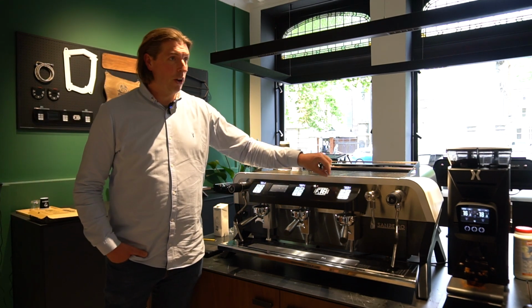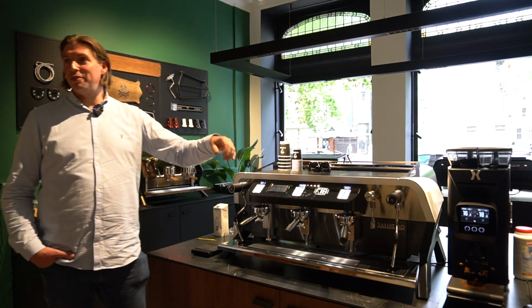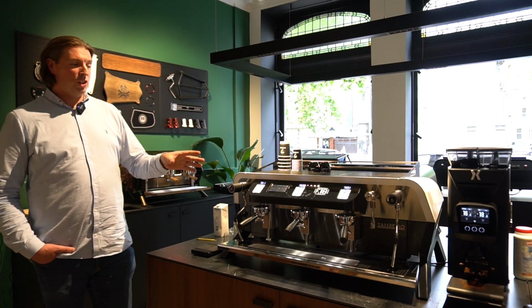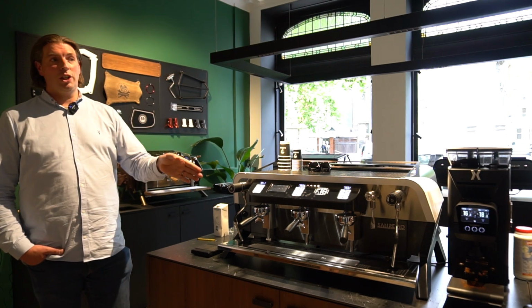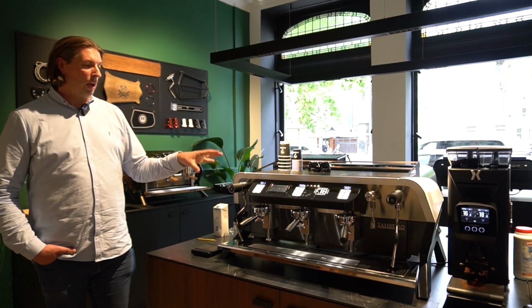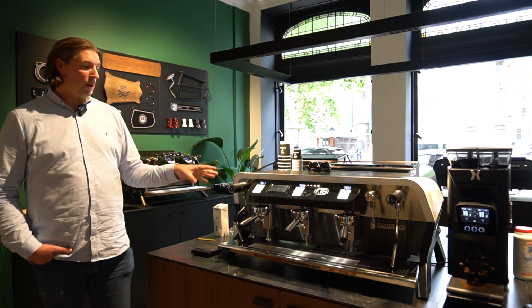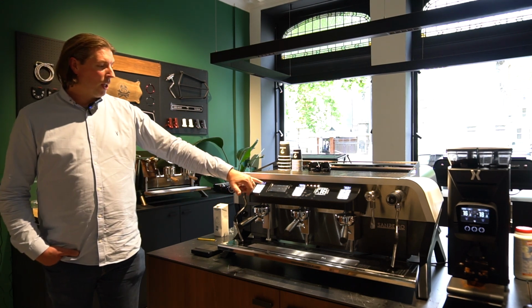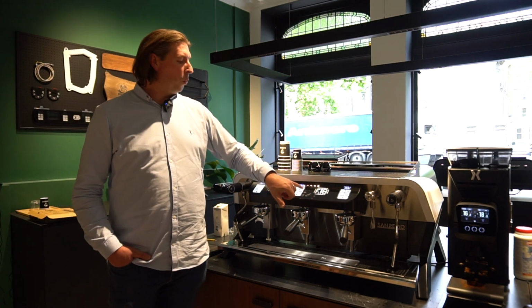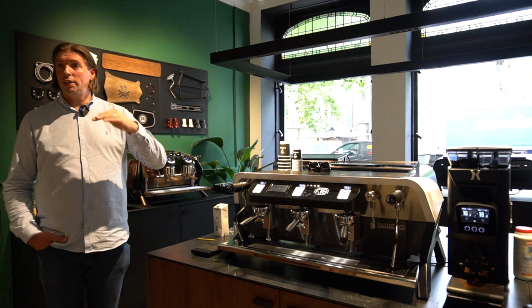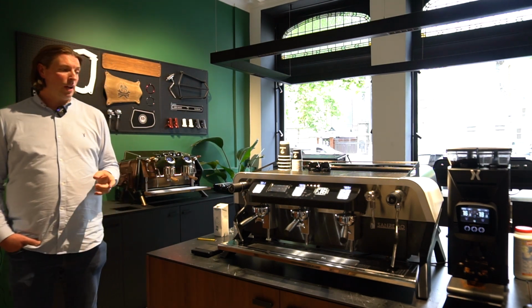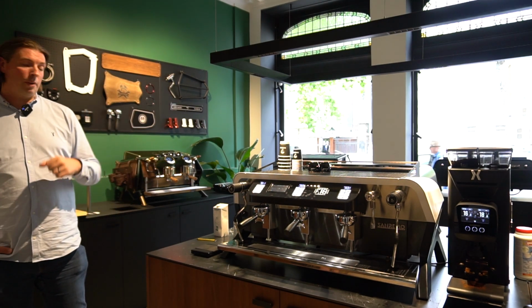So you get a lot of machines, Spaziali are great for it, that have those little LED bars with like 112 written on it or whatever, and 115. It's just what it's set to. It's not what the boiler's actually doing. Whereas we show the live point of that boiler, so you can see where the boiler's going. You can see these are all just flicking around by about 0.1 of a degree, just as they're heating up. So the stability of that group head is to about 0.1, 0.2 of a degree.